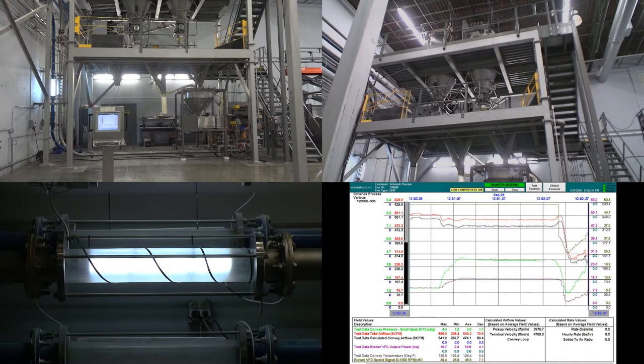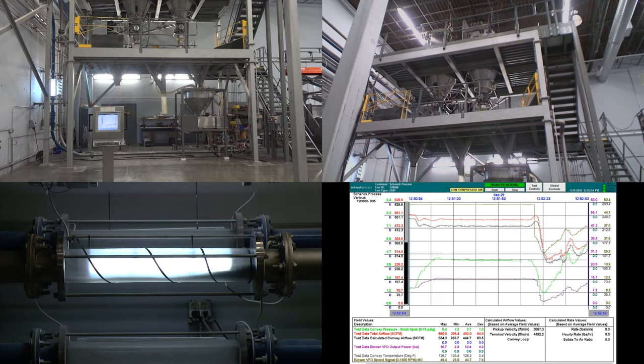When we engage the EDIP controller, we can observe a distinct difference in the flow. When we look at the operation now, we see the lowest velocity is 2,500 feet per minute. The blower is running 35 to 40 hertz, and the energy to drive the blower is around 12 kilowatts. This is a 35% reduction in velocity and 25% reduction in energy consumption.